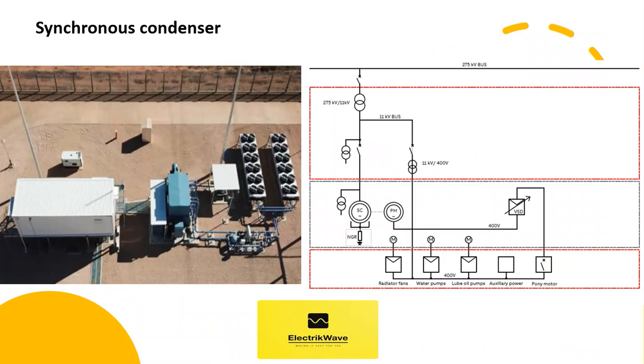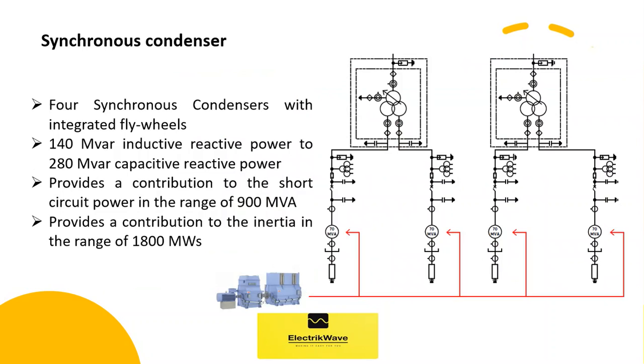Here the synchronous condenser is connected at 11 kV level and power is stepped up to 275 kV through a step-up transformer. An auxiliary transformer is tapped from the LV winding of the power transformer to feed auxiliary loads of the synchronous condenser. In this system solution, a single 3-winding transformer feeds two units of 70 MVAR capacity, so reactive power can be controlled from 140 MVAR inductive to 280 MVAR capacitive reactive power. It provides a contribution to short circuit power in the range of 900 MVA and a contribution to inertia in the range of 1800 MW.